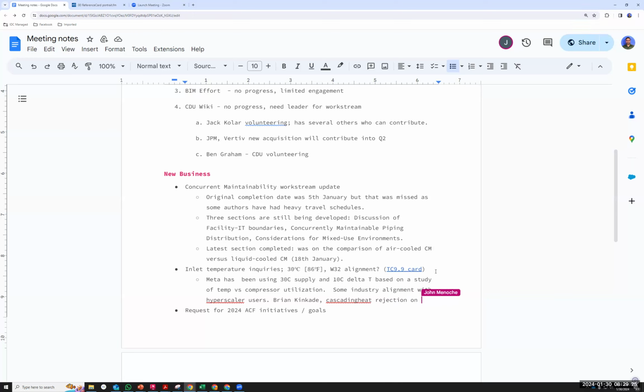And then likewise with the CDU, or bypass characteristics, allowing for mixing before returning back into that return portion of the loop is also a nice way to dampen some of those extremely higher delta T's.